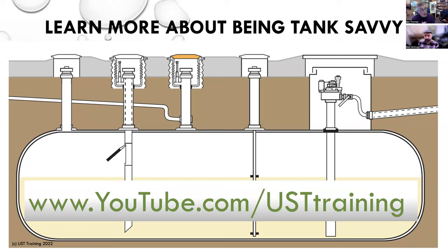So you can't just put an electronic line leak detector in and expect it to work. It has to be spec'd to the conditions, which is why once a year now, your tank gauge has to be certified by the vendor certified technician to make sure the program settings are correct. We are finding lots of settings that were tweaked in favor of the operator, but at the expense of the environment. Thank you for that, Vicky. And yes, thank you again for supporting Steve's vision. He's greatly missed.